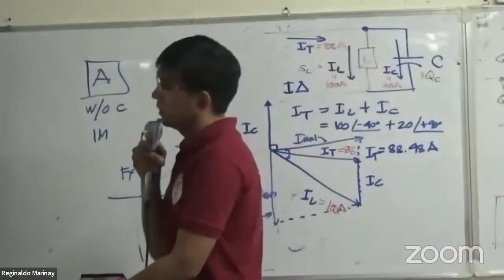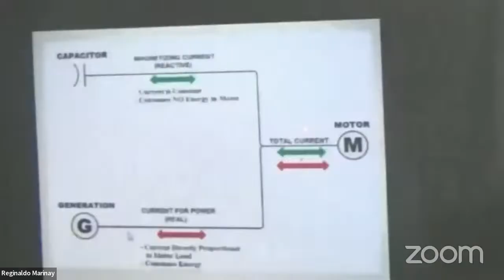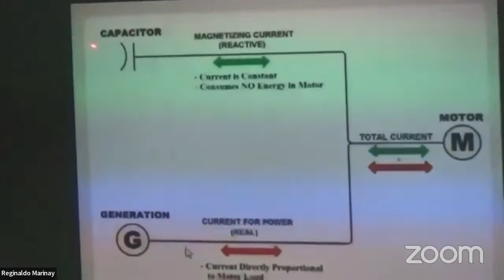I real. Real, this one. And this is your I reactive. That is your magnetizing current. Magnetizing, because that is being used for magnetization, so that there will be a rotation on the part of your rotor. So there is a capacitor here. Your motor still needs a magnetizing current. So as shown here, your generator will give you the real current. The capacitor here now will give you the magnetizing current. Because before, you're getting both from the generator. Now, since you have your capacitor, it will give you this magnetizing current.